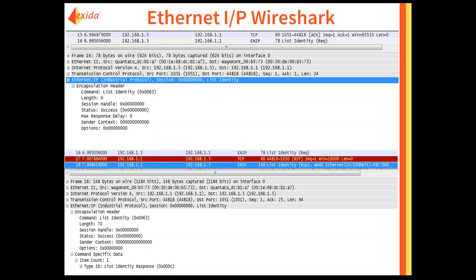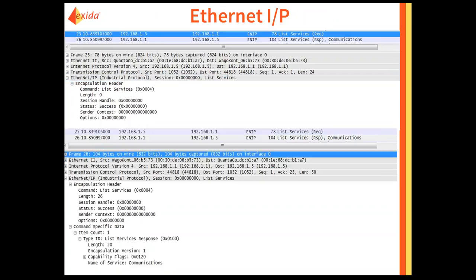Wireshark understands Ethernet IP — it knows what the protocol is and what the message information is inside the frames. Looking at a list identity request and response, you can actually see the communication going on within Wireshark to understand what Ethernet IP is trying to do. You can also list services of a device and get a response, with Wireshark interpreting the Ethernet IP protocol to tell you what it's doing.